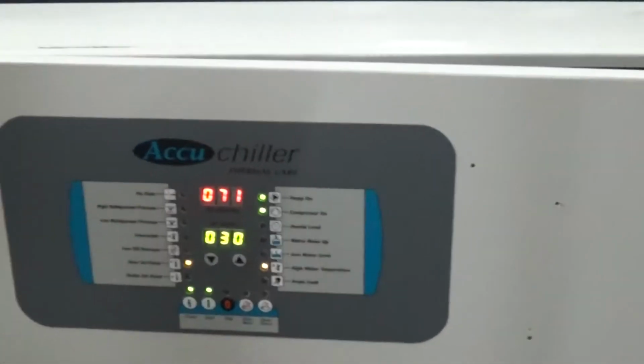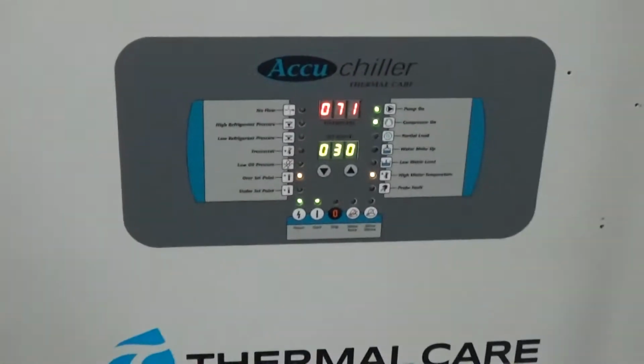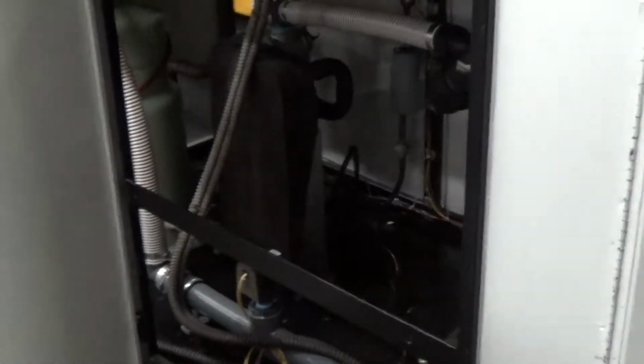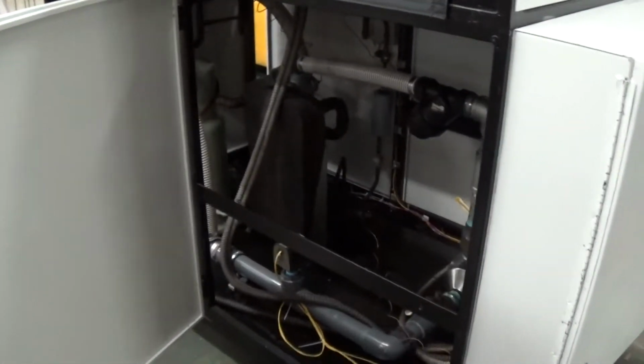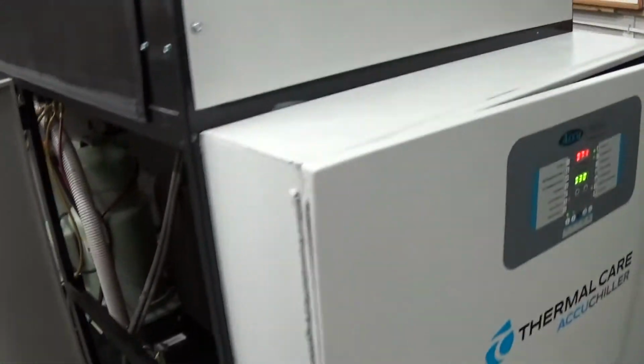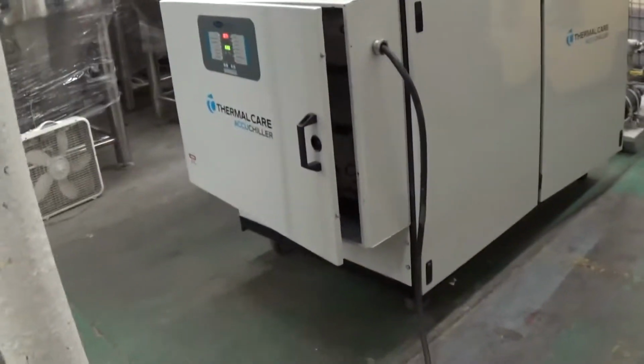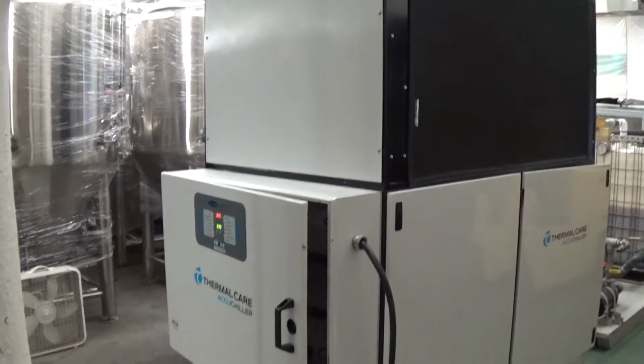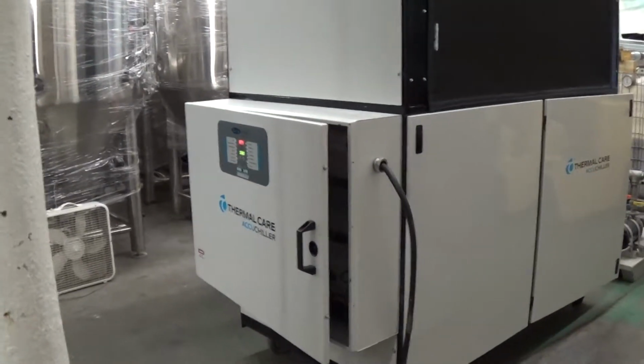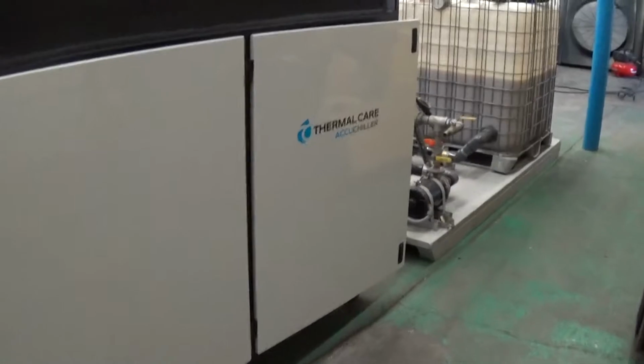When you get down to these type of temperatures, you're going to start creating frost, because what's taking place in the compressor is going to be around 10F, give or take. So you're going to start getting ice and frost on the lines in the compressor. So if you are chilling in that range, there is going to be condensation and moisture. It's our understanding that this customer wants to do a wide range of temperatures depending on their application. So the warmer the set point, the less likely you'll get that sweating.